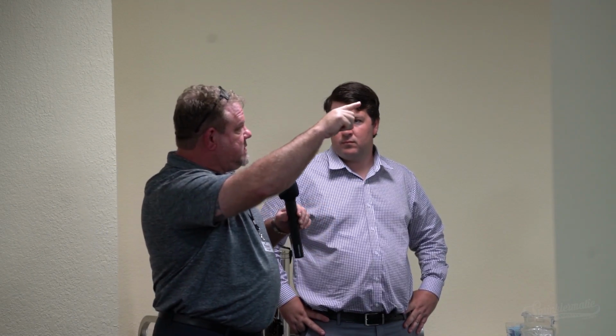And these are the less obtrusive ones? Yes, we have several different types of sprinkler heads. This is a concealed type, more desirable for me, with less impact to the building. We've got semi-recessed heads that protrude a little from the ceiling, which you'll see in the carport area. Because it's non-conditioned space, we use a semi-recessed head to give corrosion resistance, so we don't have issues in the future. We're right across the street from the ocean, so that's a nickel Teflon coated head.